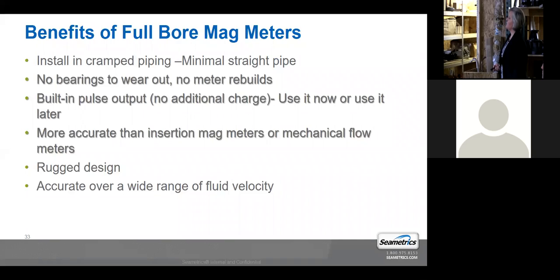They're more accurate than insertion meters or mechanical meters. They're just a rugged meter, and they're accurate over a wide range of fluid velocity. When you look at mechanical flow meters, they typically require a minimum flow rate flowing through that water to get that mechanical component turning fast enough to get an accurate reading. So a lot of times you look at a manufacturer specification and it'll say, let's say on an 8-inch meter, that it will require 100 GPM minimum, just to get the prop turning so that you get some sort of reading on the meter.